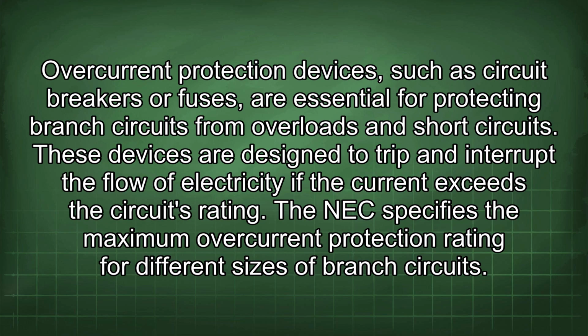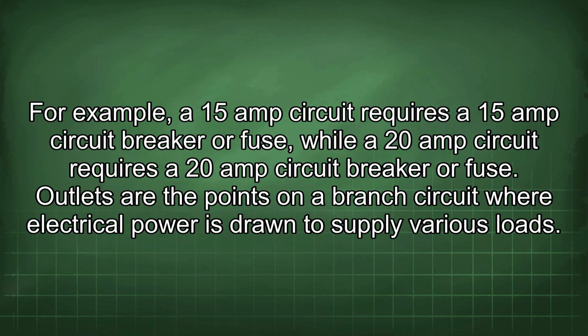Overcurrent protection devices, such as circuit breakers or fuses, are essential for protecting branch circuits from overloads and short circuits. These devices are designed to trip and interrupt the flow of electricity if the current exceeds the circuit's rating. The NEC specifies the maximum overcurrent protection rating for different sizes of branch circuits. For example, a 15-amp circuit requires a 15-amp circuit breaker or fuse, while a 20-amp circuit requires a 20-amp circuit breaker or fuse.